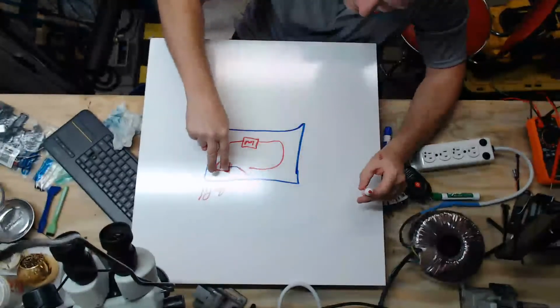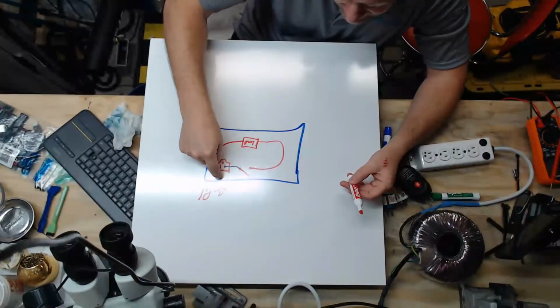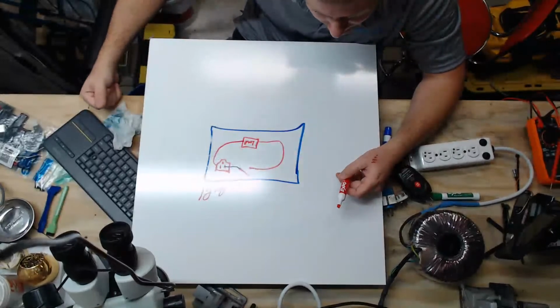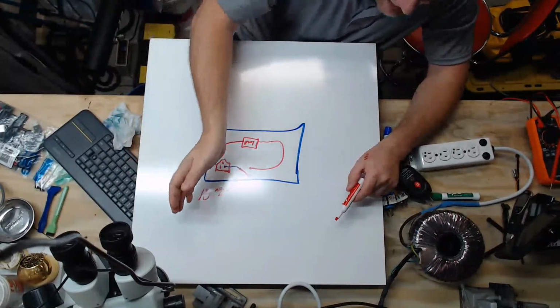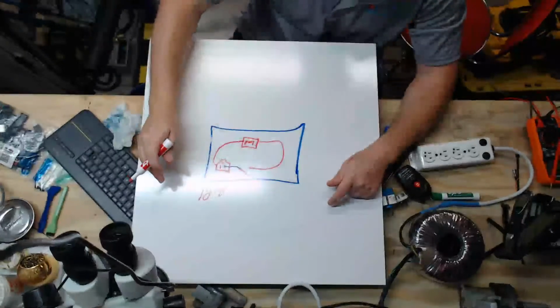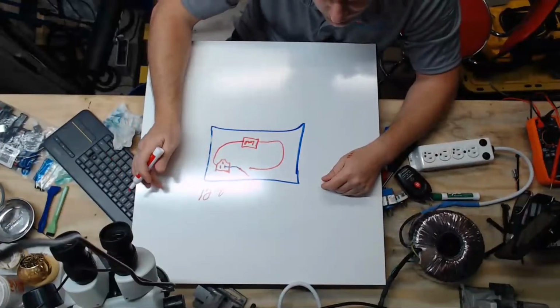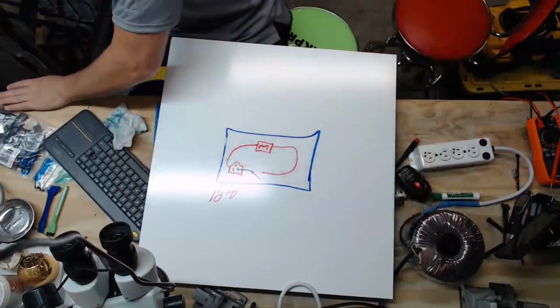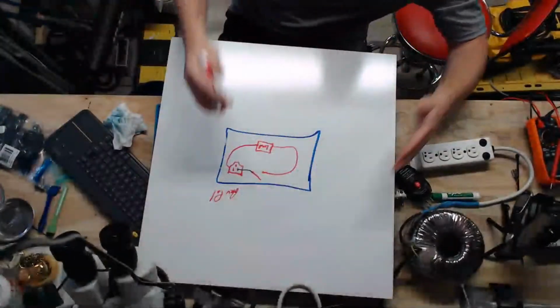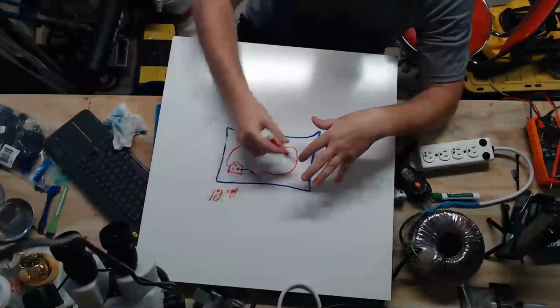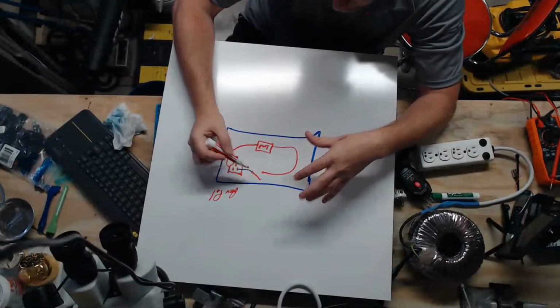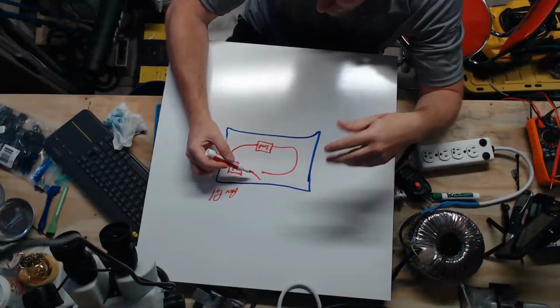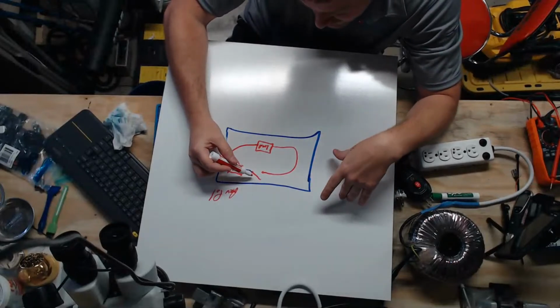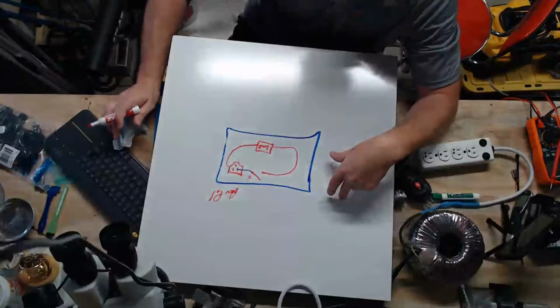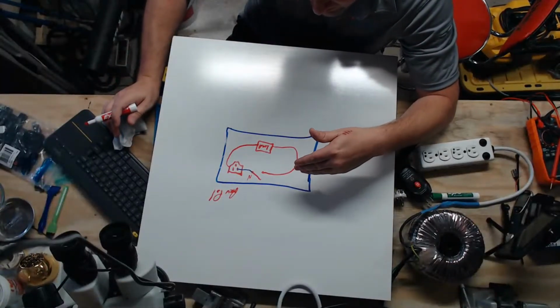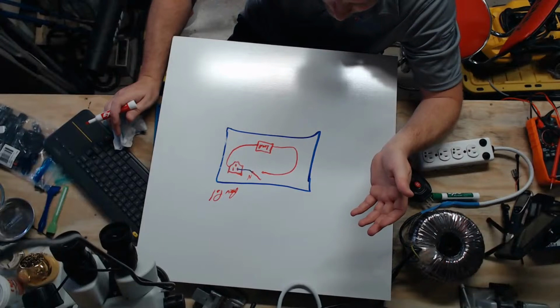If you fail to connect those two wires on the inside of your medical device in the correct polarity, you just negated every single one of those safety features that is built into your standard electrical code. Okay. Hold on. So the bad thing about all this is if your entire device is hot and your power switch here is now reverse polarity and it's neutral, then that means you could honestly zap yourself by even touching this device.